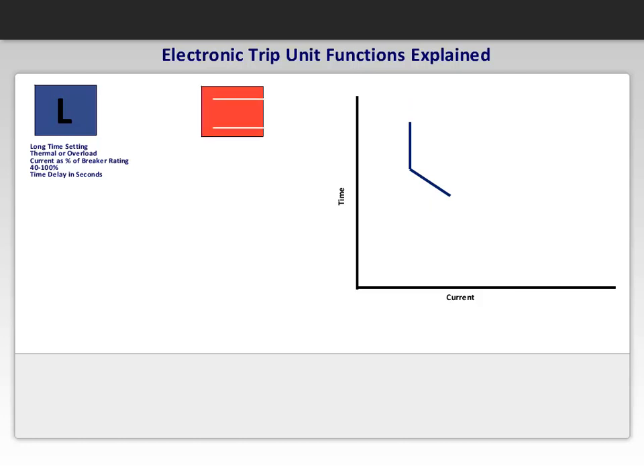Next is S, which stands for Short Time. This setting is associated with the magnetic or short circuit setting, and is set as a multiple of the breaker rating, usually 1 to 10 times, and can be bypassed for just an instantaneous setting. It is represented by the red line on the curve. It, too, can be moved in and out along the current axis, and up and down along the time axis.